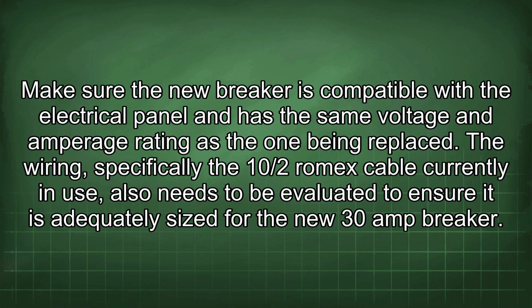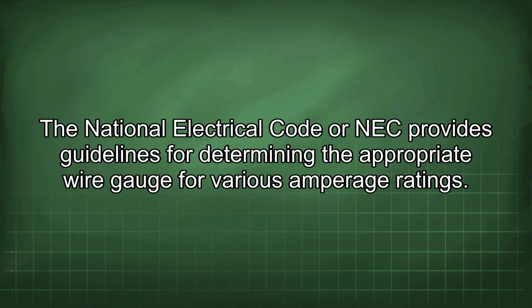Make sure the new breaker is compatible with the electrical panel and has the same voltage and amperage rating as the one being replaced. The wiring, specifically the 10/2 Romex cable currently in use, also needs to be evaluated to ensure it is adequately sized for the new 30 amp breaker. The National Electrical Code or NEC provides guidelines for determining the appropriate wire gauge for various amperage ratings.